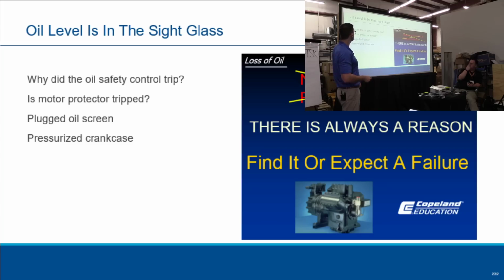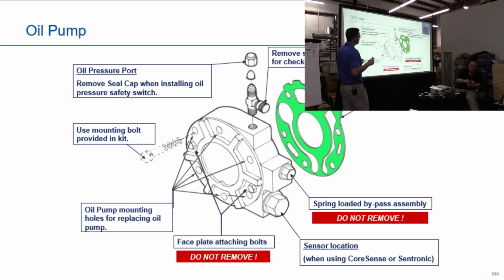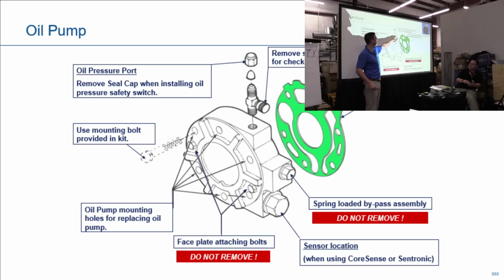Oil level in the sight glass. Why did the oil safety trip? Nuisance trips of oil failures? There's no such thing as nuisance trips. Something caused it to trip. This is an oil pump. One thing that you need to be aware of as a technician, you have on the side here a Schrader. On the top you put your oil pressure port. If you pull this off, what's going to shoot in your face? Oil. Make sure you're always checking the oil pressure from the side here.